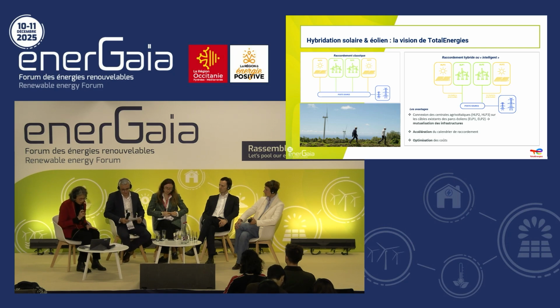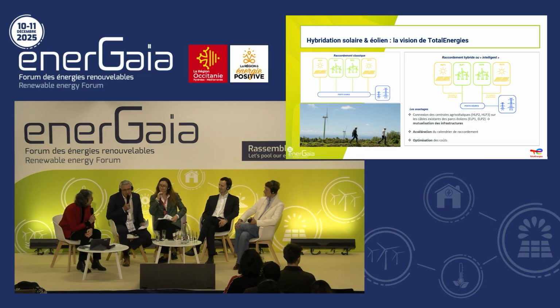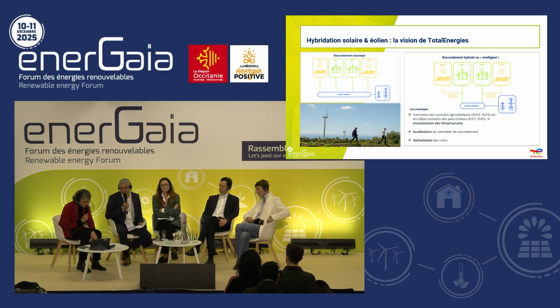Isn't there a constraint linked to this clipping? I think Enedis grants you a 5% clipping maximum, and you need to clip at 7%. Well, yes, I didn't go into that level of detail, but there was a dual constraint: we couldn't go below 70% of the installed power, and we could not clip more than 5%. We sought a dual derogation to go below 70% and to clip a little more than 5%. In this case, it's between 7 and 8%, which remains very low and acceptable.